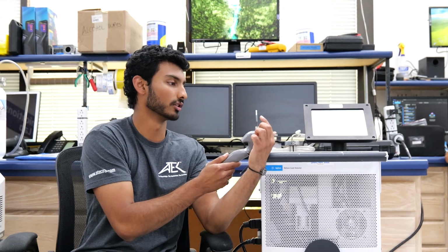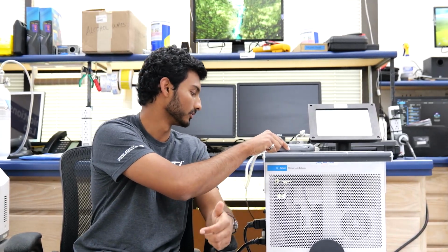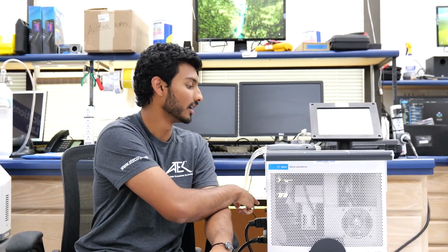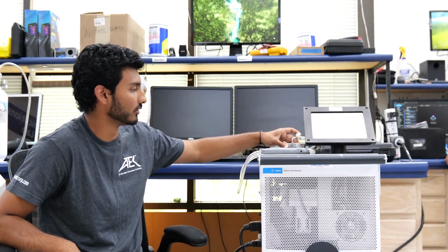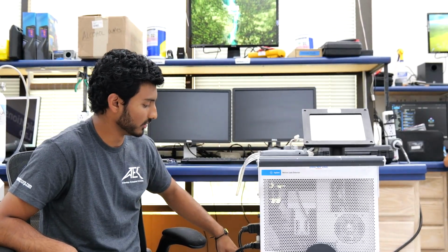Always check your inlet filters. As you can see, there's a filter on the actual sniffer probe, and there's more filters inside of the unit. Sometimes these filters can get blocked and can cause issues. And then finally, checking the hose connections. As you see, we have hose clamps between the pumps. Sometimes they can come loose, so make sure to check that everything is tight.